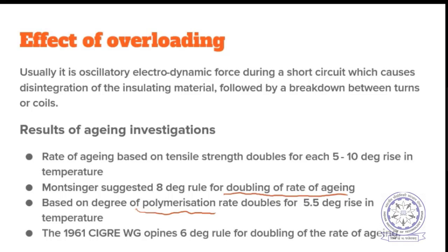which is a measure of the strength of this paper insulation, abbreviated as DP, it gives in some way the strength of the polymer chains in the paper. So how strong or how long the chain is. It will give an indication of the strength of the material indirectly. So based on the degree of polymerization, the aging is estimated such that for every 5.5 degree rise in temperature, the rate of degradation is expected to double. So these are the results of all investigations until now.